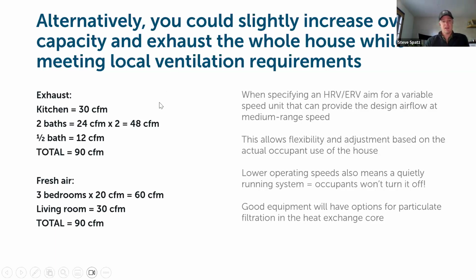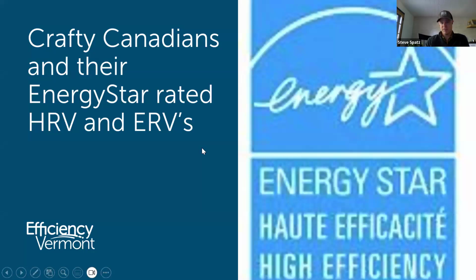So in this example again here, we're looking at breaking down our 90 CFM of exhaust throughout the building as 30 CFM coming from the kitchen, 2 full bathrooms getting 24 CFM of exhaust, and then the half bathroom of 12 CFM. So that all balances out to 90 CFM on the exhaust side. On the fresh air side, putting 20 CFM into each of the 3 bedrooms, 30 into the living room, and then again, that getting us to an equivalent 90 CFM for supply side. So this is a way of looking at designing for the whole system, balancing it out from exhaust to supply, and getting again to an equivalency that aligns with what the ASHRAE calculation gave us for total building ventilation needs.